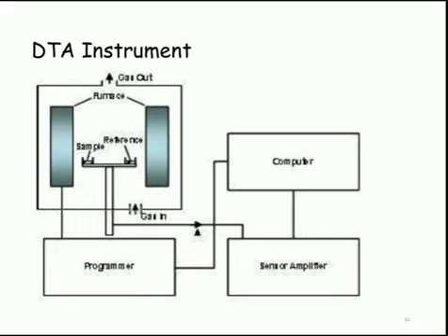This is done either by increasing the voltage through the heater element by a motor driven variable transformer or by a thermocouple actuated feedback controller.